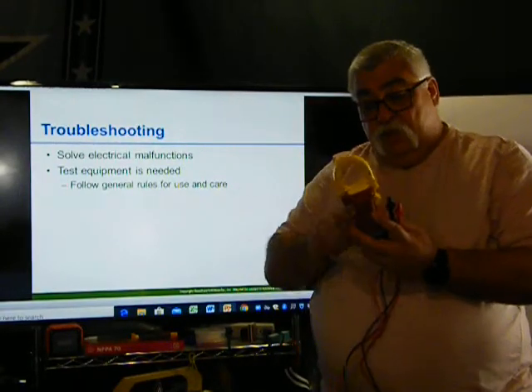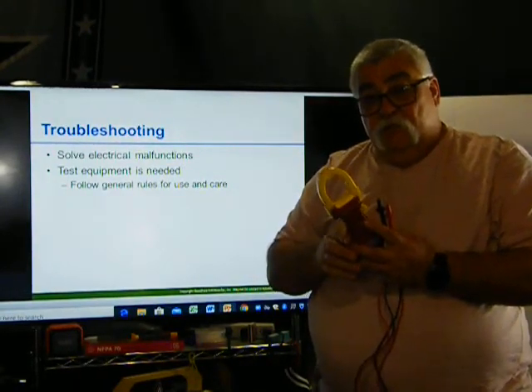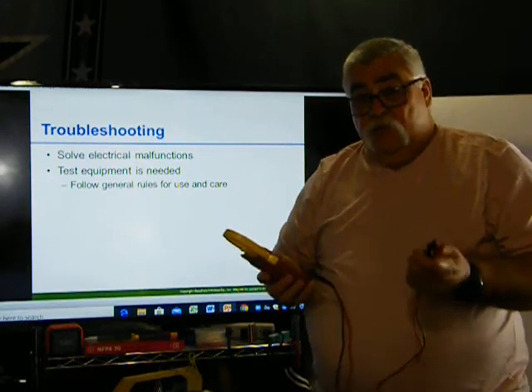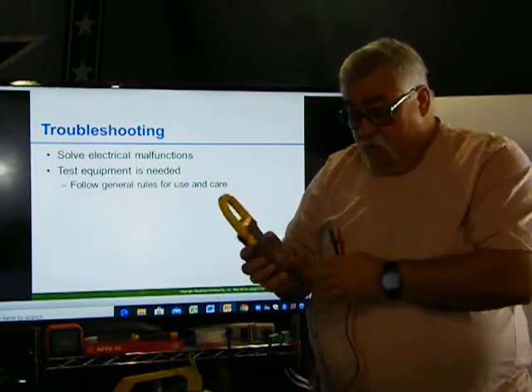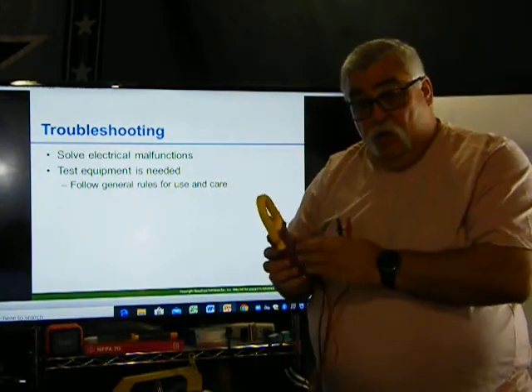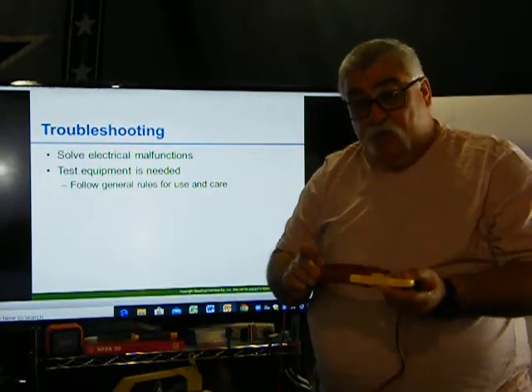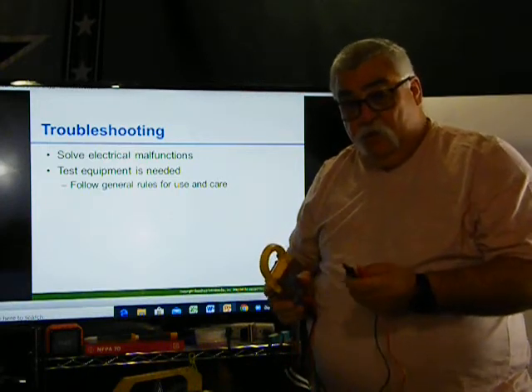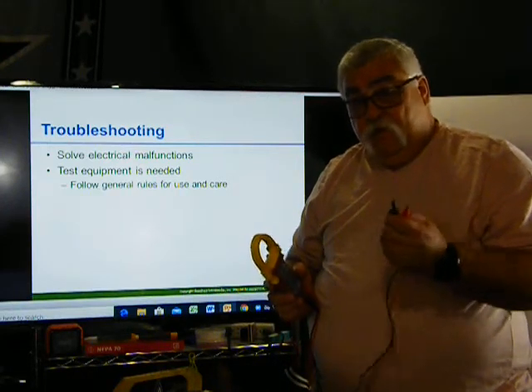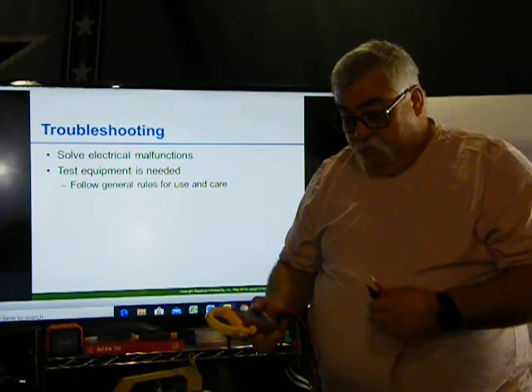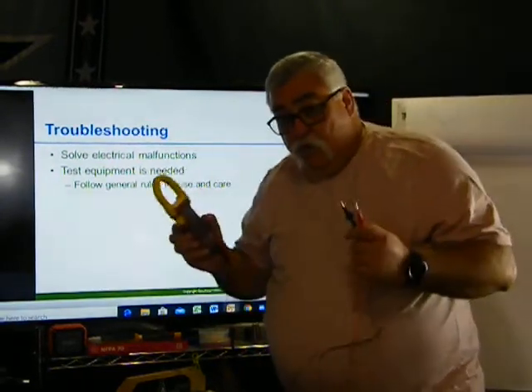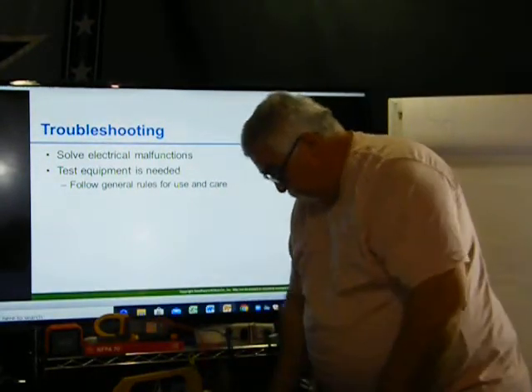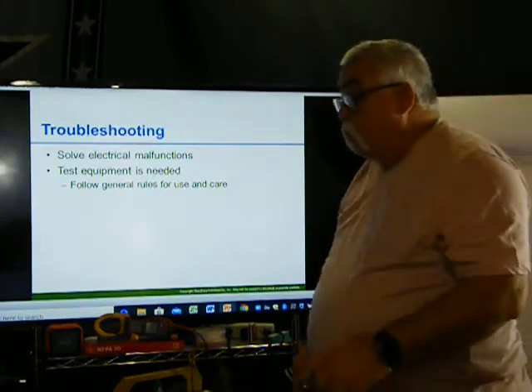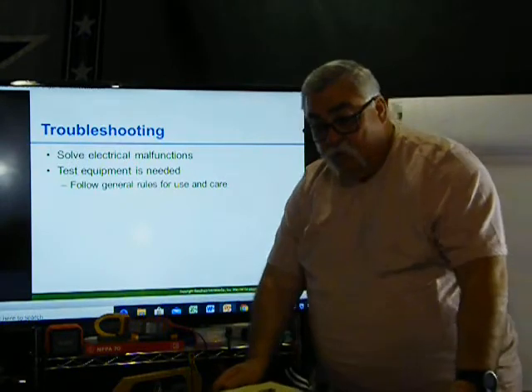What this does is it sends out a voltage signal. Then it gets back, that's how it reads the resistance. Okay. So it sends out a signal and it comes back. Well, a lot of these have a fuse inside to protect it in case voltage does go in. Okay, so it does have a fuse to protect in case it does. So you have to be very careful when you're doing resistance testing, or continuity. Check it for continuity. Okay, make sure power is off. Make sure power is off. Voltage, no voltage present. No voltage present.